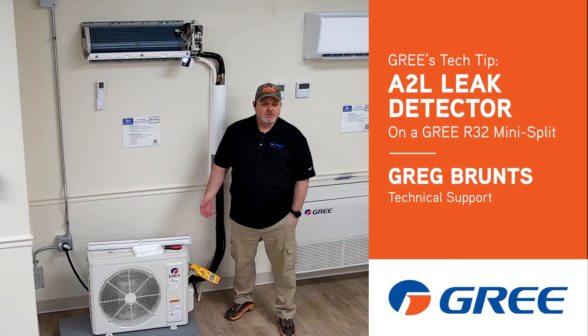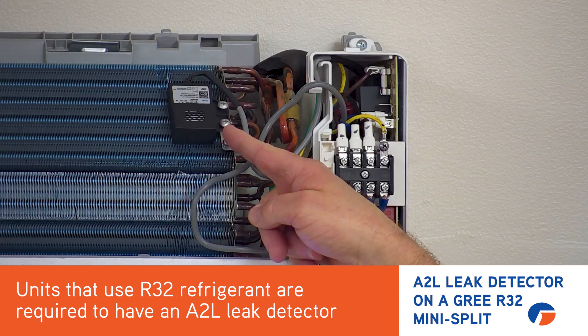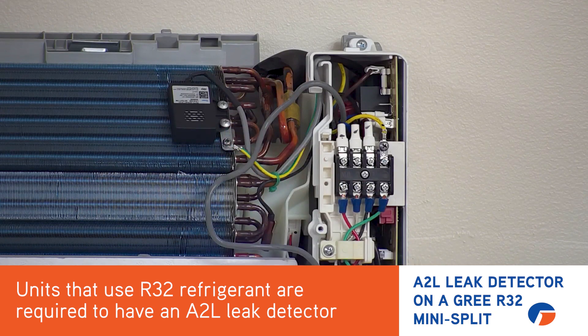Hi, Greg with GREE with another quick tip for you. What I have here is a new R32 mini split — this is actually the Levo series. Since it is R32 refrigerant, we do have to have the A2L sensor on it, because R32 is a mildly flammable refrigerant.